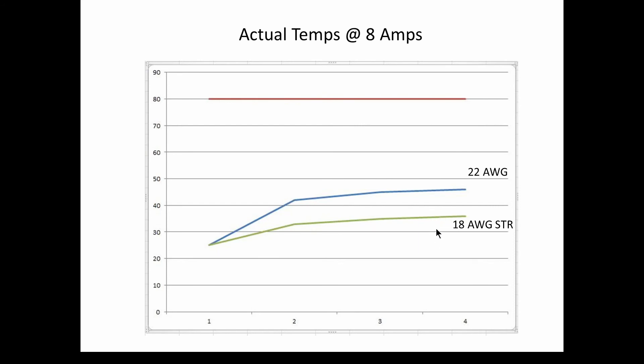So, my only point here is, don't immediately assume when you see a table or somebody says the rating is this, don't immediately assume it applies to your situation or every situation out there. Maybe not. Now, maybe they are using, in the tables, they're using a very conservative number. Maybe they worry about, we did it with a wire that's out in the open. Even if you put them into a box or a power supply or something, there's going to be an ambient that's much higher. So, that could affect it.